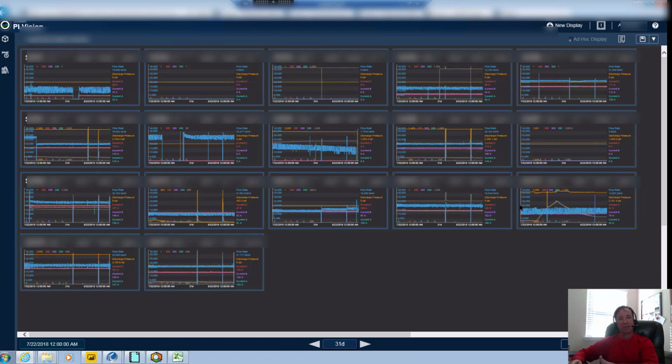And we actually ran into something here just this week where doing simple analytics in real time in the PI system can actually help you find potential problems. So if you look on this screen, this is a dashboard that one of our customers looks at every single day. This is something that's templatized. They're using collections in PI Vision to understand what is going on with certain pieces of equipment. And they're looking at things like pressures, flows, temperatures, currents, things like that.